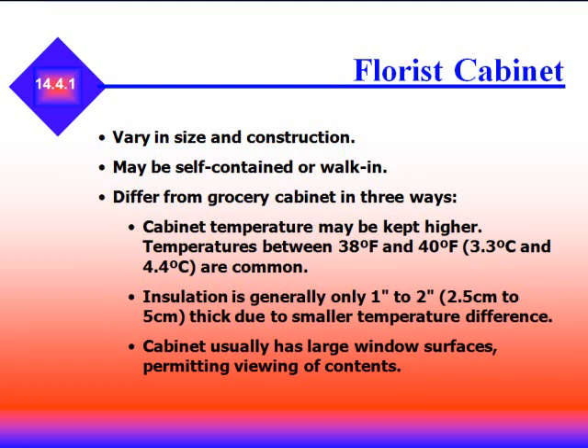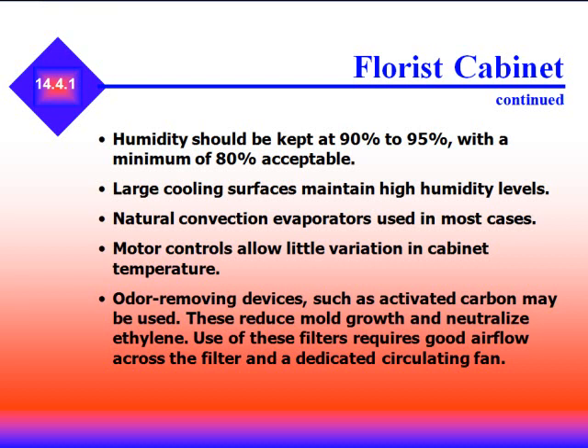Florist cabinets, found in front of grocery stores or in floral shops, vary in size and construction. They may be self-contained or walk-in. They differ from grocery cabinets because cabinet temperatures are higher — 38 to 40°F — insulation is smaller at 1 to 2 inches, and cabinets usually have large window surfaces to permit viewing of contents. Humidity should be kept higher at 90–95%, with a minimum of 80%. Natural convection is used in most cases without fans. Odor-removing devices such as activated carbon may be used to reduce mold growth and neutralize ethylene that plants emit, which causes them to spoil. These filters require good airflow and a dedicated circulating fan.